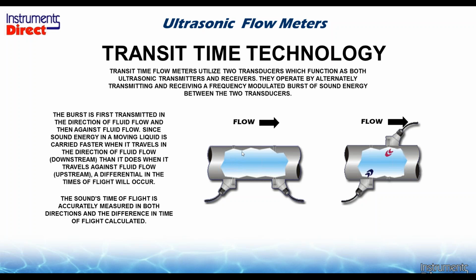In this case, we're lazy. We're using 2 sensors on the same side of the pipe and ricocheting the pulse off the back wall. The reason to do that is it's convenient to see both sensors, and it's convenient to align both sensors. So life is just a whole lot easier when you can install it on the pipe in this configuration. This type of configuration is called the V, or the dual path configuration. And this configuration to the right is called the Z, or single path configuration. These are traditionally associated with pipe sizes.